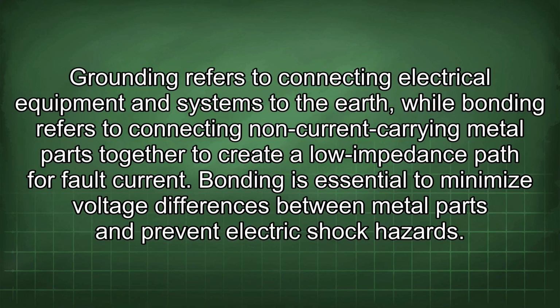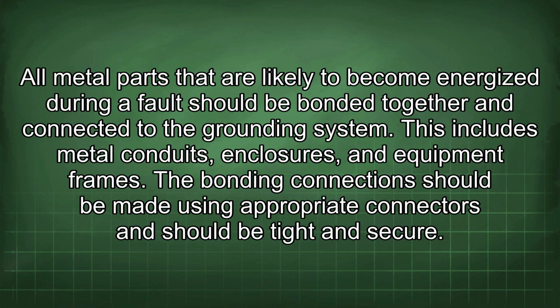Grounding refers to connecting electrical equipment and systems to the earth, while bonding refers to connecting non-current carrying metal parts together to create a low impedance path for fault current. Bonding is essential to minimize voltage differences between metal parts and prevent electric shock hazards. All metal parts that are likely to become energized during a fault should be bonded together and connected to the grounding system. This includes metal conduits, enclosures, and equipment frames.